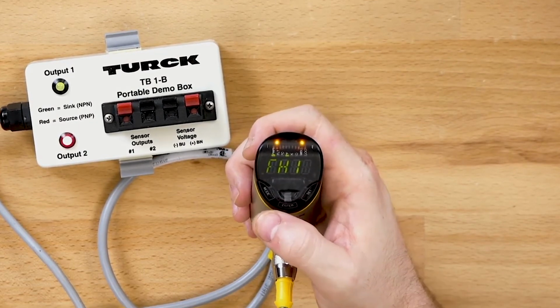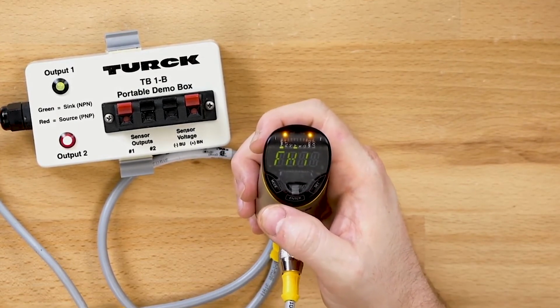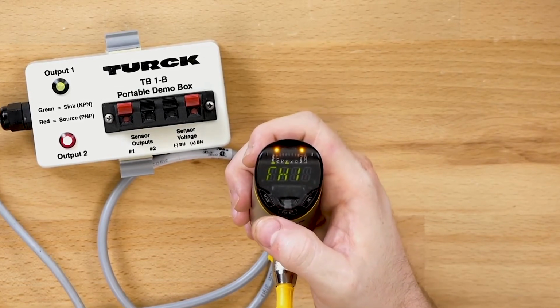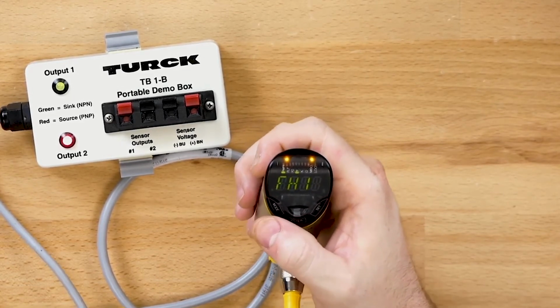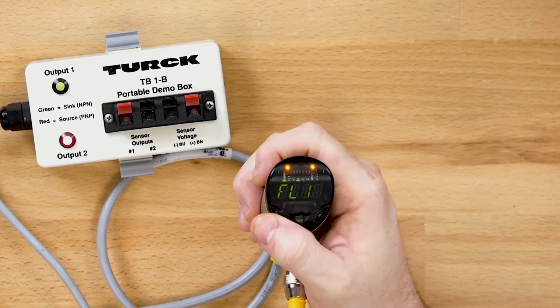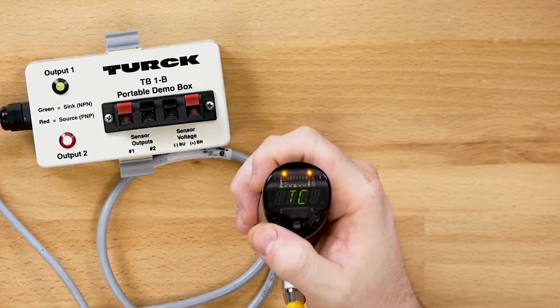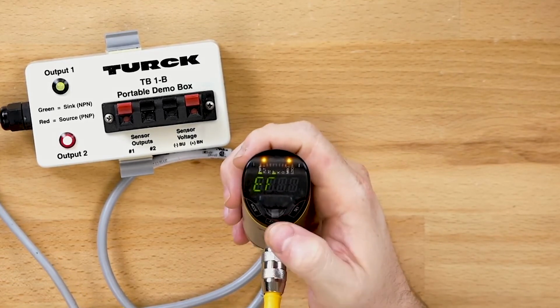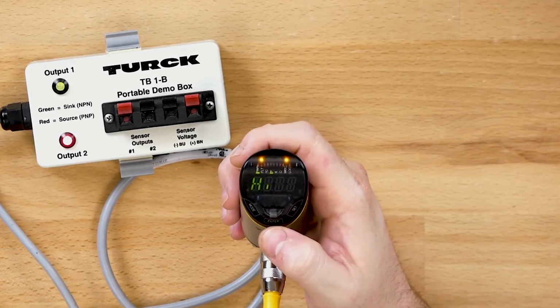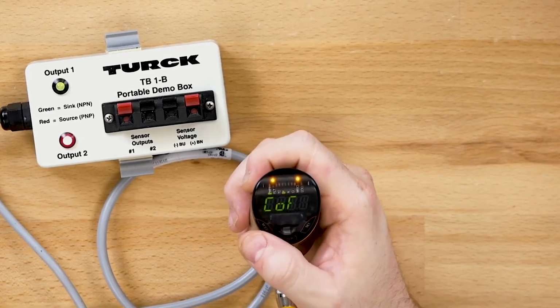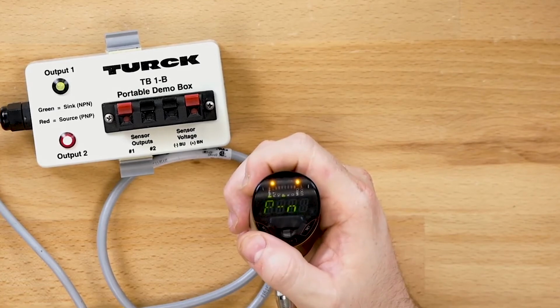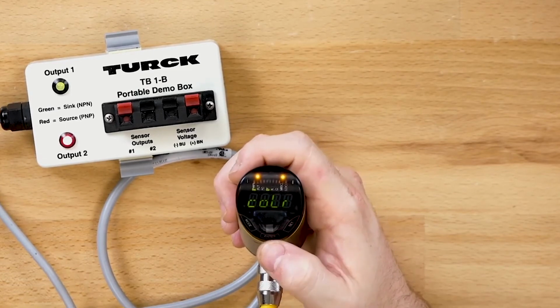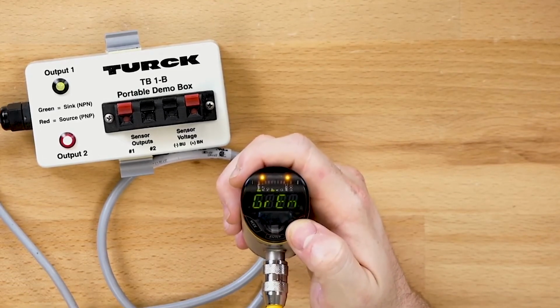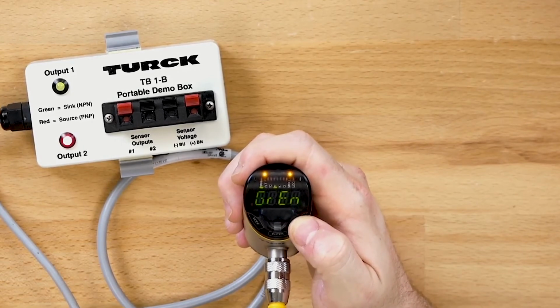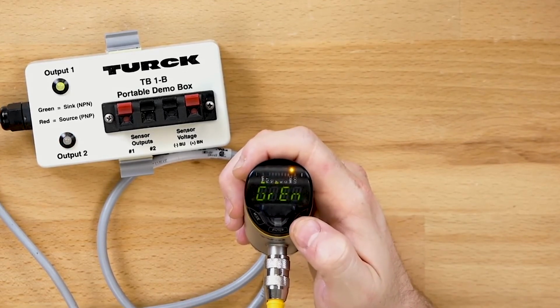Let's also set the sensor to turn red when the temperature goes below 30 degrees or above 80 degrees. In the main menu, we'll use the Mode and Set buttons to navigate to the EF submenu. Using Enter to enter the menu. Using the Mode and Set buttons, navigate to the color menu and press Enter. Again, holding the Set button for 3 seconds until the display stops blinking is going to allow us to change this parameter.